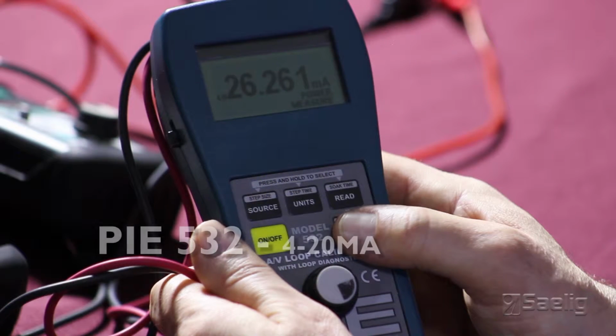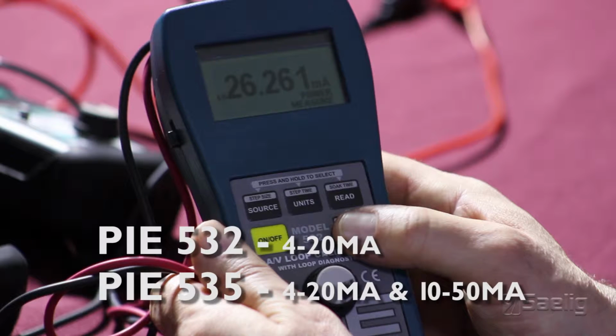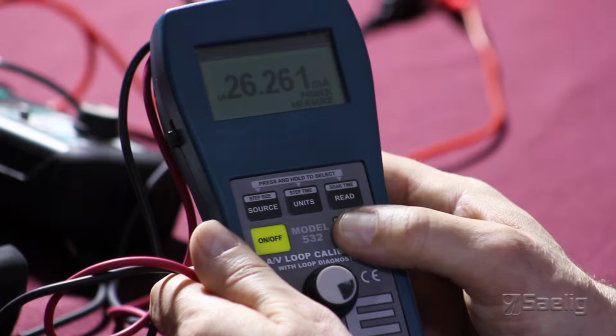PIE also has two calibrators which source and read voltage along with sourcing and reading current. The PIE 532 for 4 to 20 milliamp loops and the PIE 535 which does 4 to 20 and 10 to 50 milliamps. 10 to 50 milliamps still being used in some of the older power plants.